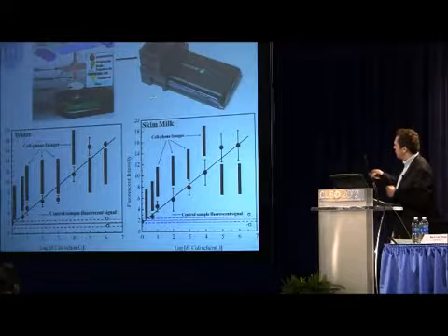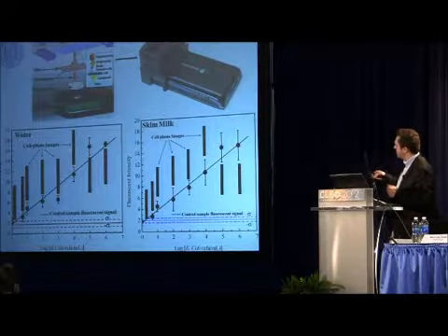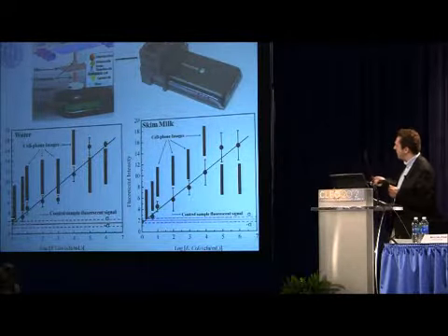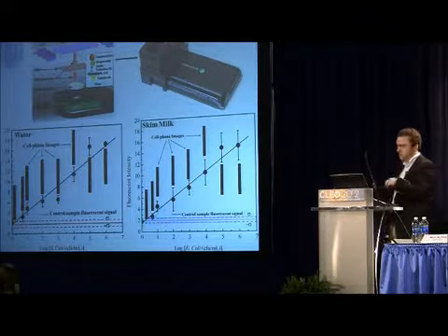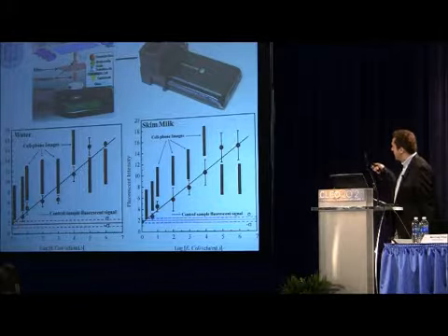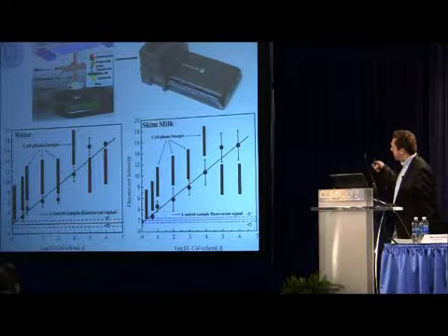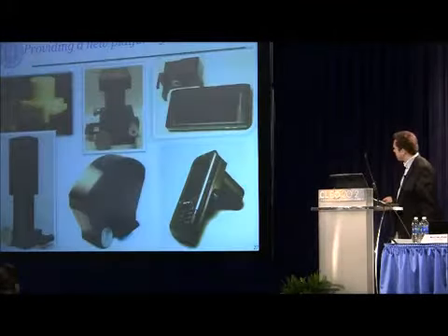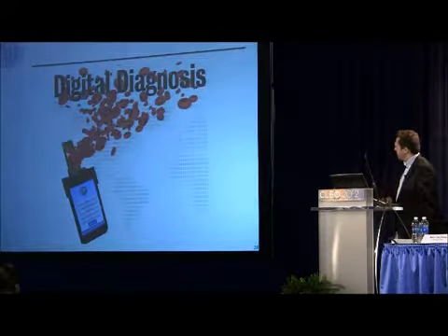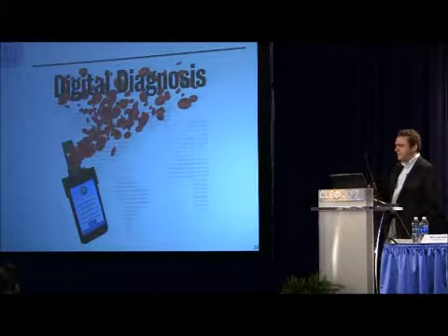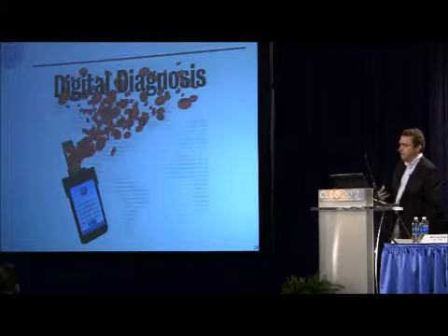And we've determined the detection limits using some tests on skim milk and water, and the results turned out to be around 5 to 10 colony-forming units per milliliter, which is quite good considering the compact and field-portable nature of these devices. And recently we've introduced some other technologies that also benefit from the computational power and the connectivity of the cell phone.